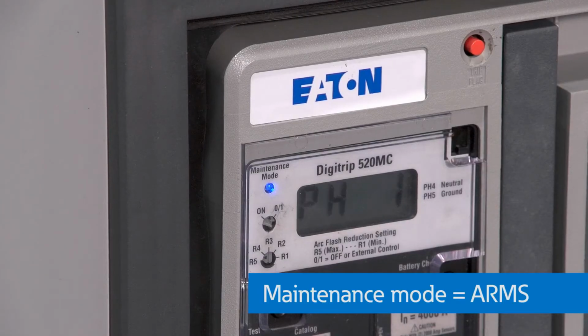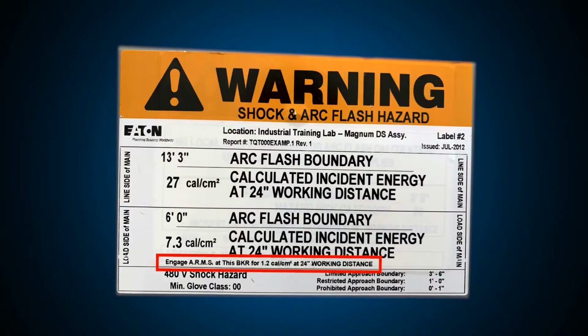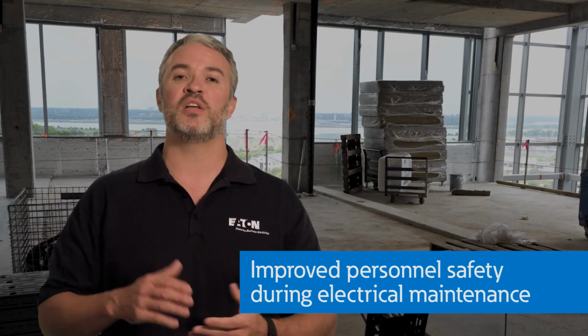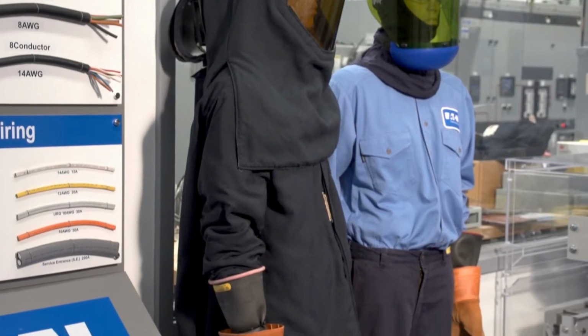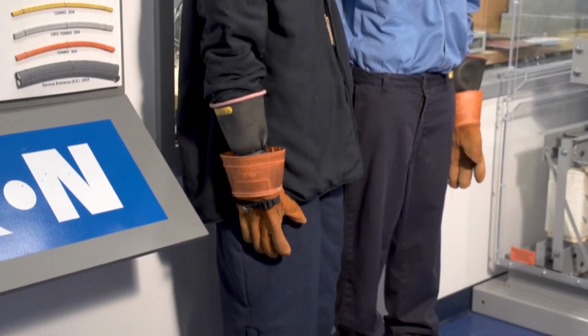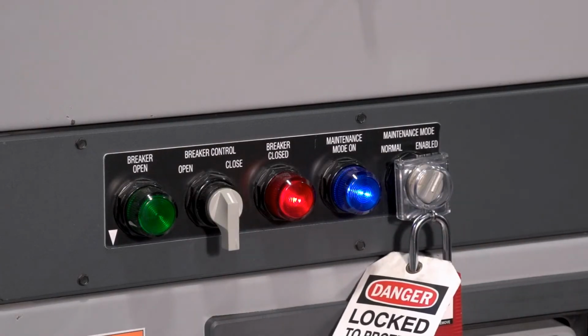The system may be activated at the breaker or from a remote location. The result is a reduction of the incident energy during equipment maintenance, allowing for improved personnel safety while eliminating the need for higher levels of costly PPE. With a lock applied at the breaker during your LOTO procedure, you can ensure that you are protected while working on downstream equipment. For most power systems, the highest level of arc flash energy on low voltage switchgear is on the source or the line side of the main circuit breaker.